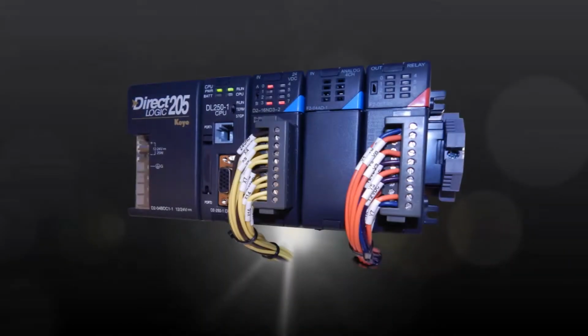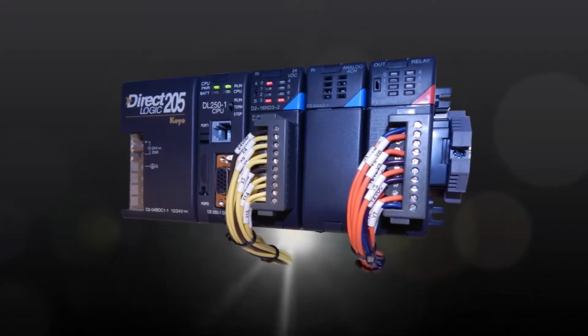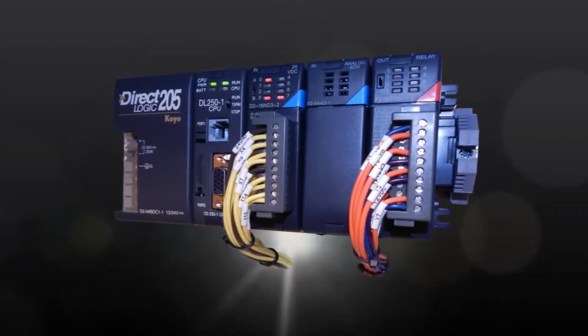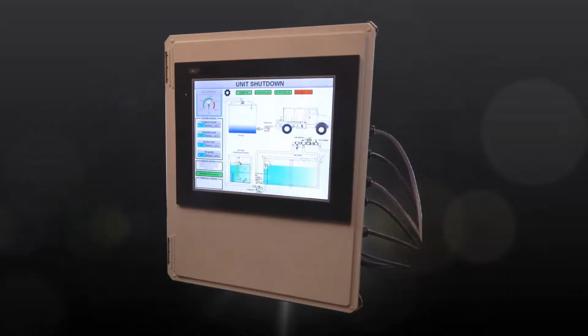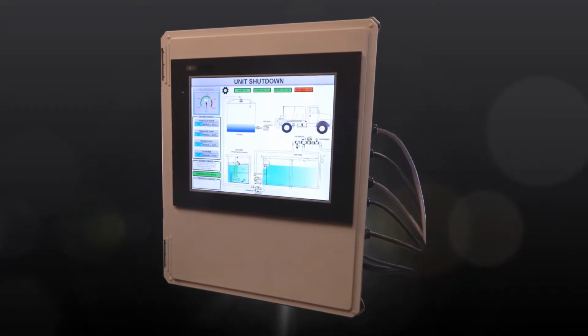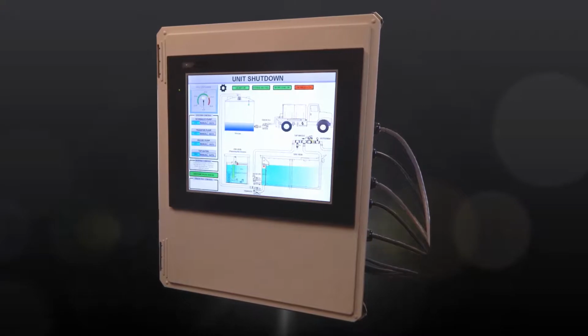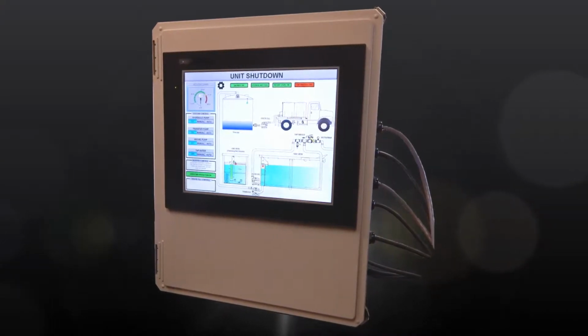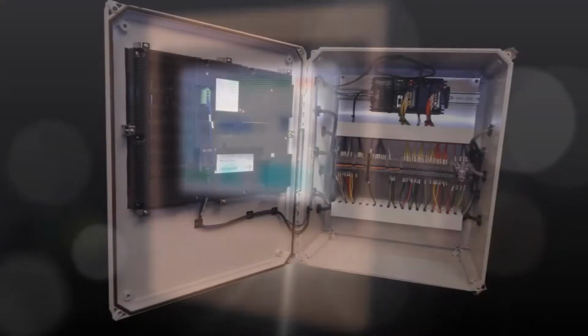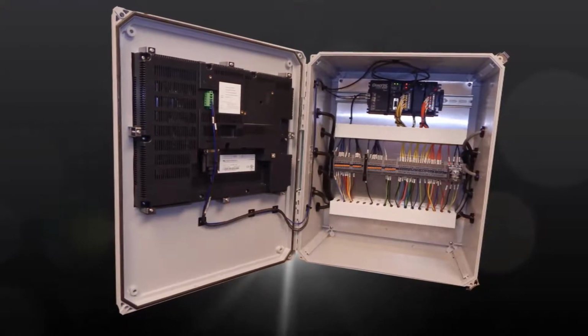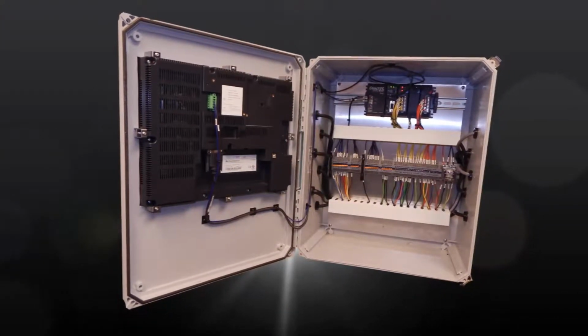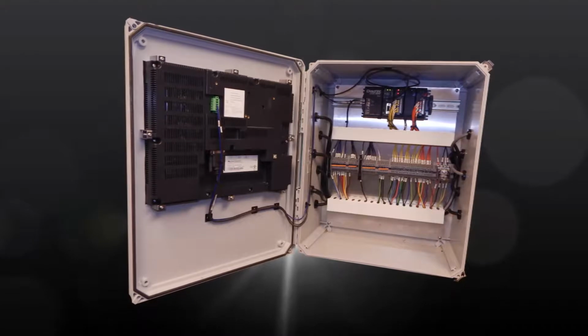The Penguin EasyBrine is a fully automatic system controlled by an industrial programmable logic controller. The PLC monitors brine levels in the hopper and storage tanks, salinity level, and truck fill demands to create, store, and dispense brine automatically. It also monitors outdoor temperature to recirculate brine and prevent freezing at low temperatures.